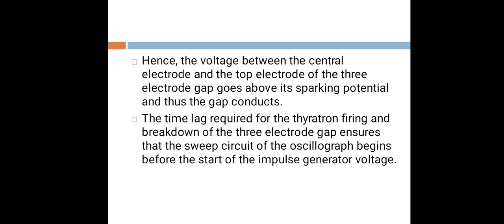Hence, the voltage between the central electrode and the top electrode of the three-electrode gap goes above its sparking potential and thus the gap conducts. The time lag required for the thyratron firing and breakdown of the three-electrode gap ensures that the sweep circuit of the oscilloscope begins before the start of the impulse generator voltage.